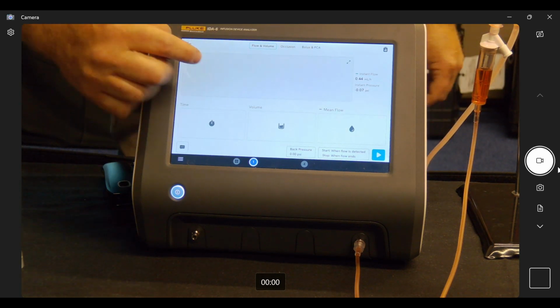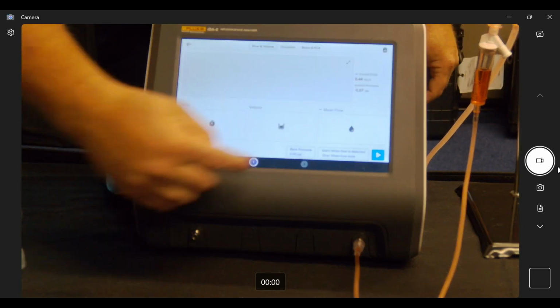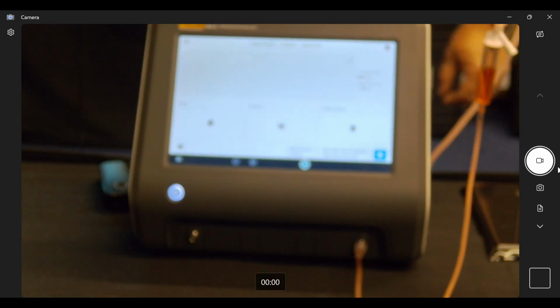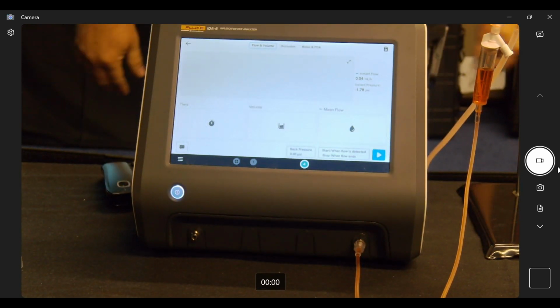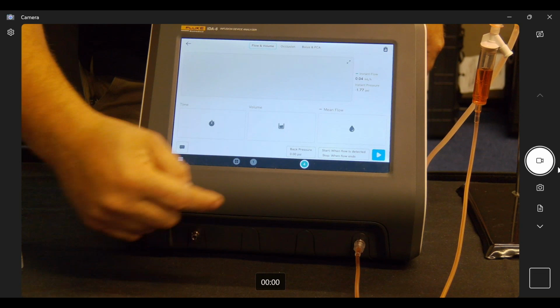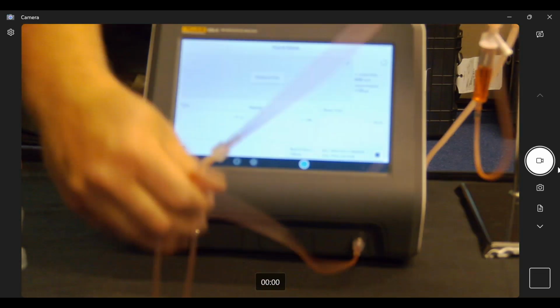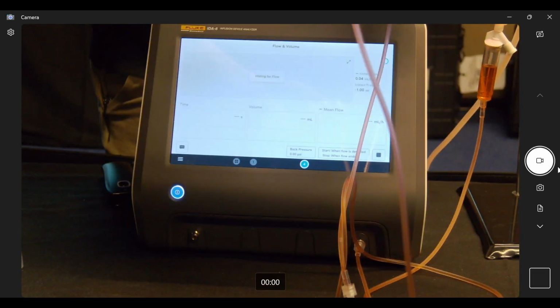So let's go to our flow and volume channel 4, because that's where I'm plugged in. Key thing about running analyzers: wherever you have an inlet, make sure you have an outlet, or you have a very wet bench, and a calibrated towel has to come into play. I'm going to hit run here and open up this line.